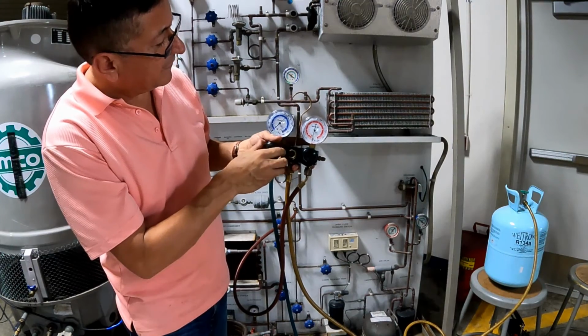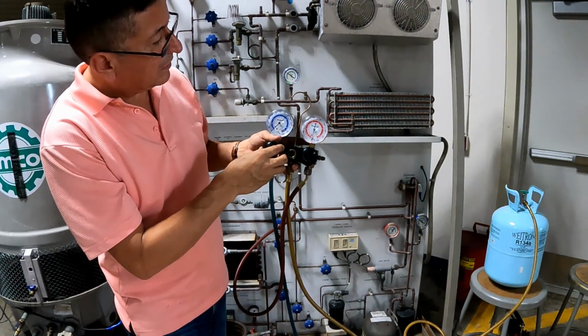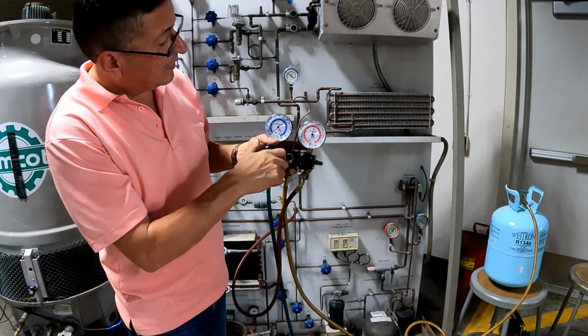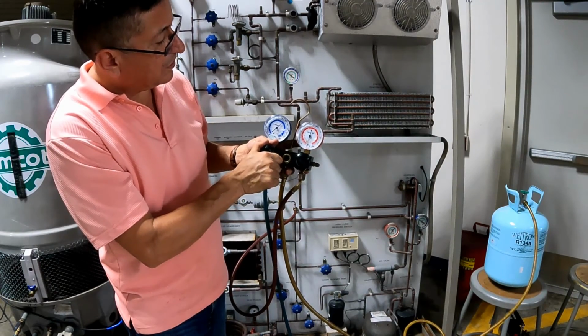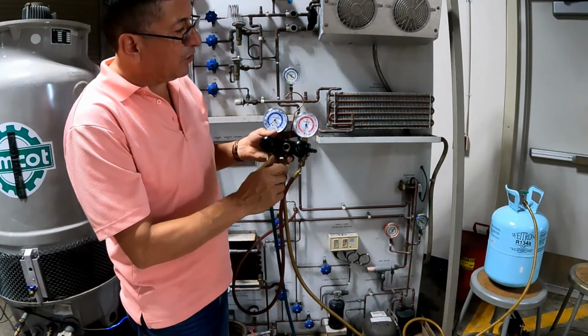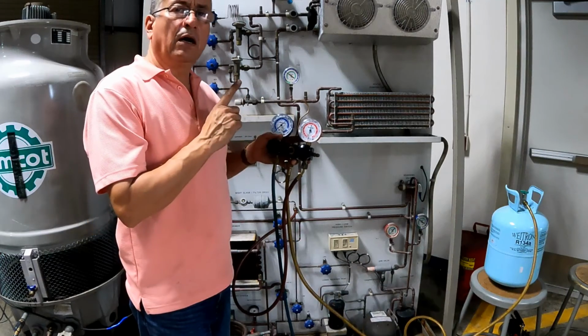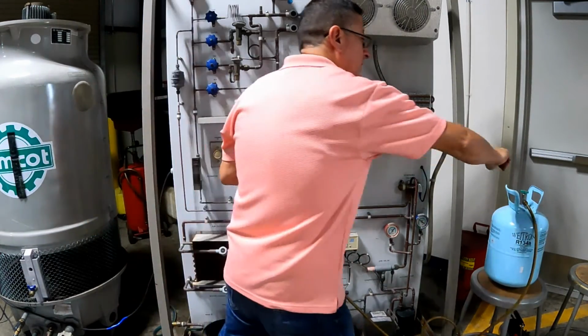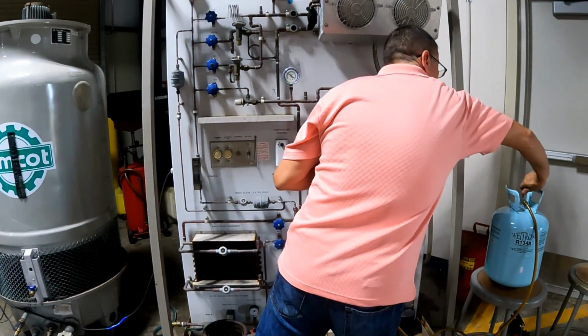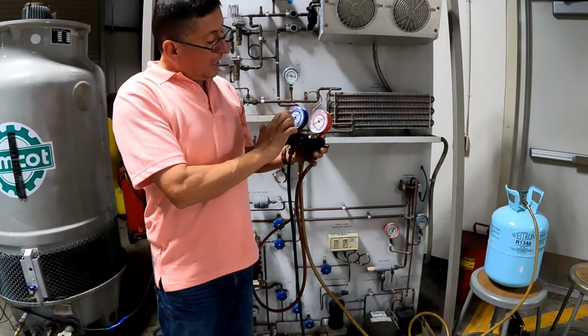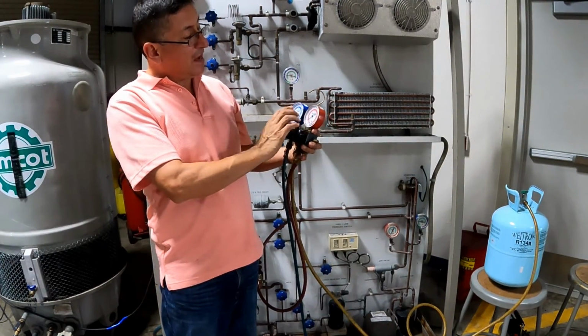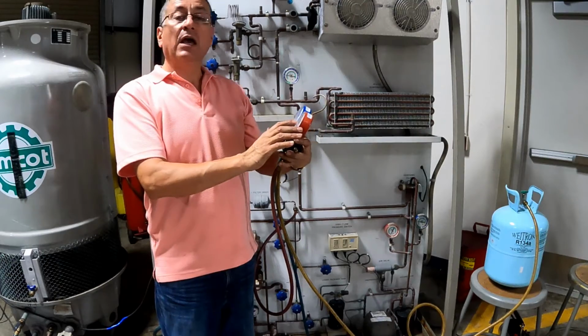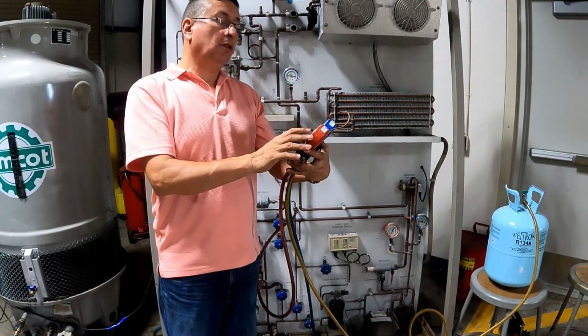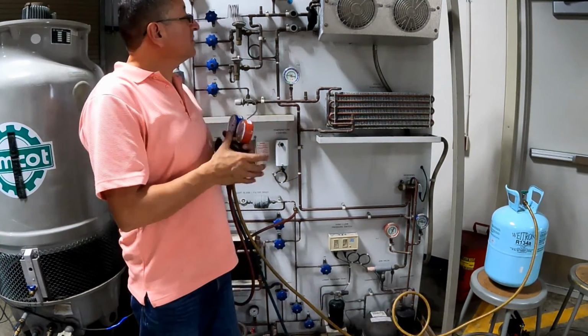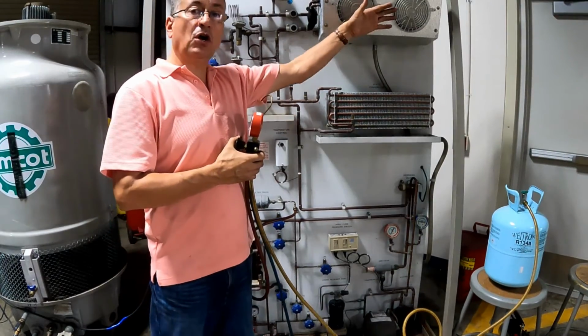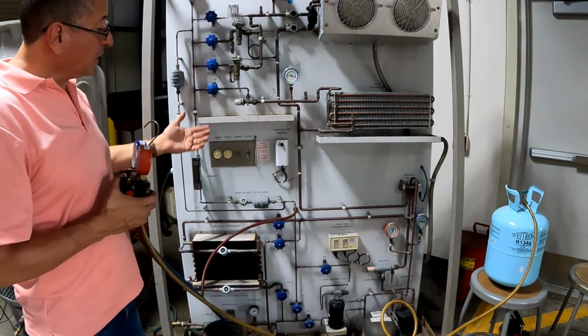Increase a little. And go down. And right now, I am going to close the cylinder. Okay, right now, the low pressure side is 60-65, and the high pressure side is 225-230 psi. The system is ready, the air is cold, and the system is working properly.